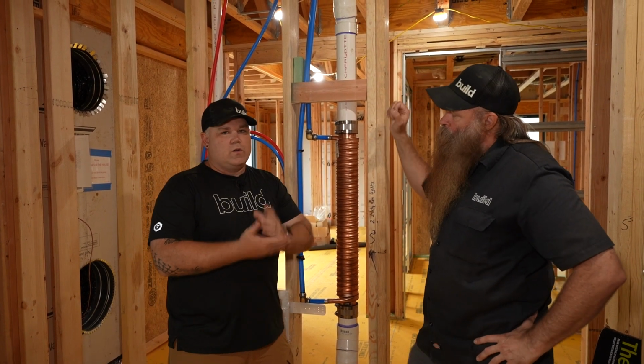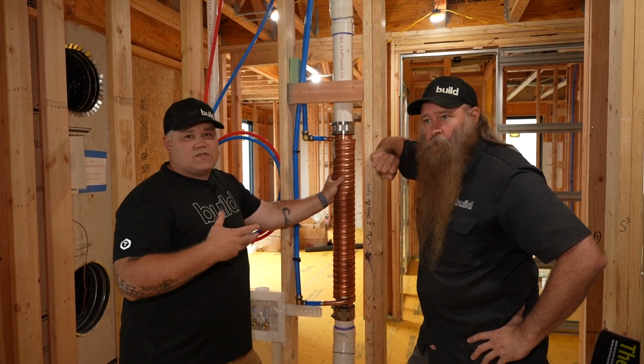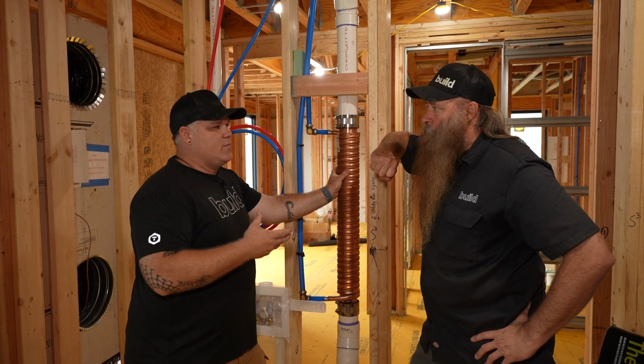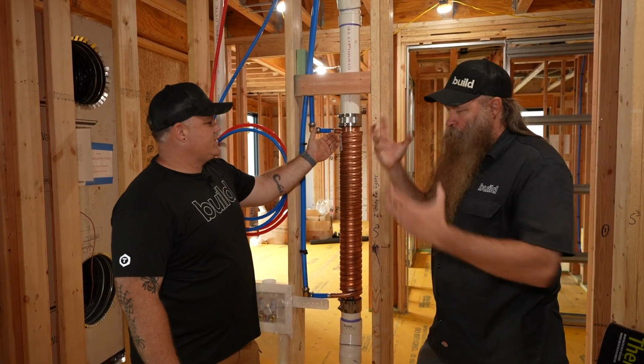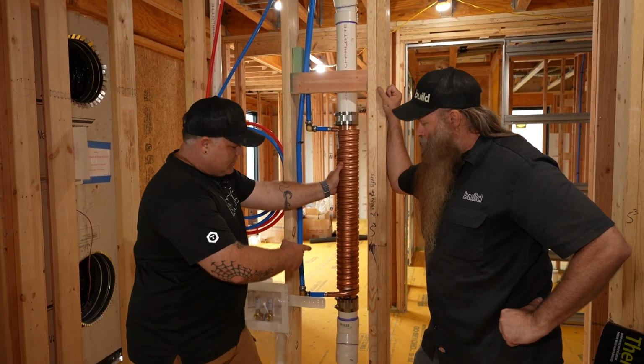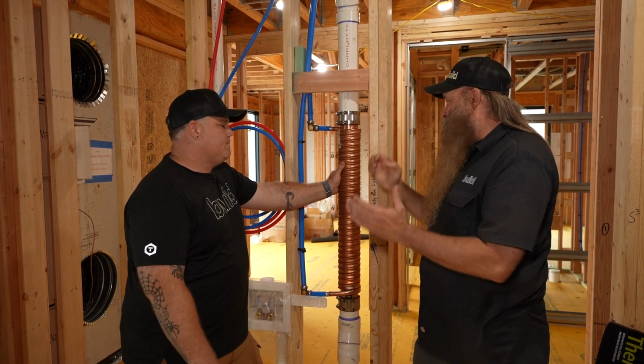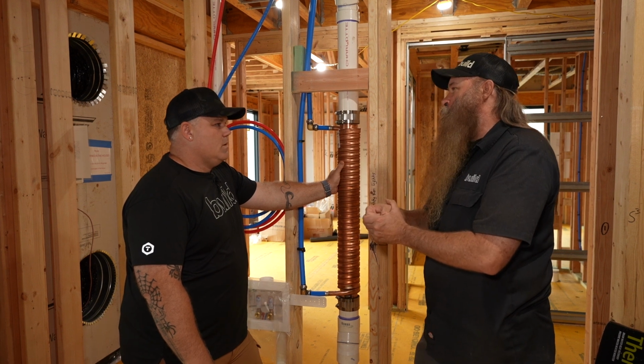So what we're looking for is an application where this shower piping is going to run through it, right? Typically that's where it's most reliable that hot water is going to be going down the drain. Right. We're going to capture, or transfer, that heat that's in the wastewater already into the potable water in this 3/4-inch type L tubing. Type L is what we're used to. Yeah. Well, but it's changed because it's flattened. We're not seeing it in its normal round state.